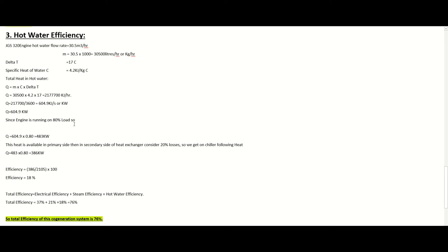Since the engine is running at 80 percent load, we get heat according to 80 percent, which is 483 kilowatts. This heat is available on the primary side of the jacket water. To extract this heat we install a heat exchanger; due to heat exchanger losses of about 20 percent, we get 386 kilowatts on the secondary side. So the output in case of hot water is 386 kilowatts. The input is the same as in previous cases — the kilowatts of gas supplied to the gas engine (2,105 kW). Dividing output by input: 386 ÷ 2,105 = 18 percent efficiency.